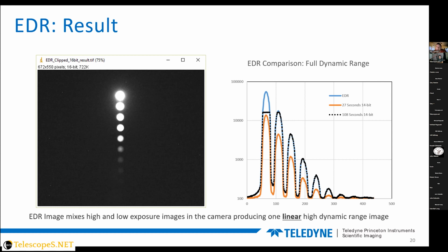Well, if you only collect 200 photons, your maximum dynamic range is 200 if you have a perfect camera, right? You're not going to be able to resolve more than one photon because that's a discrete quanta. And with some nice cameras and setups, you guys are getting down to taking images that only have a few hundred photons in them. And if that's the realm you're operating in, you don't have any dynamic range, right? You could buy the highest dynamic range camera in the world, and it's not going to help you. In that case, you need quantum efficiency, you need low noise. And dynamic range can actually work against you in that scenario.